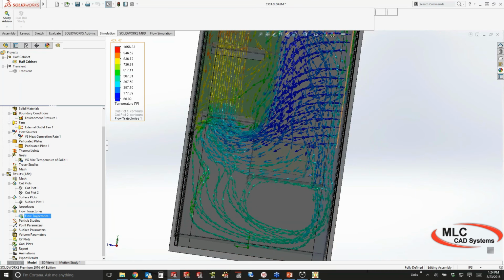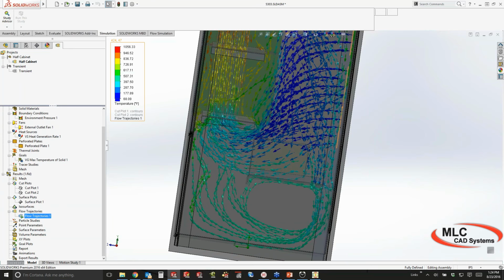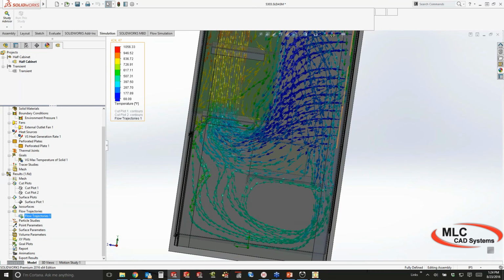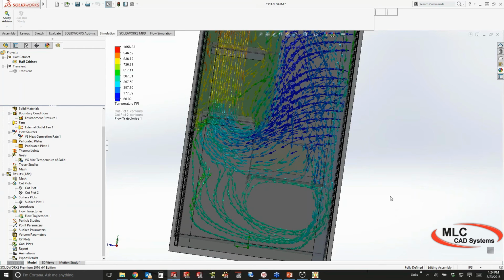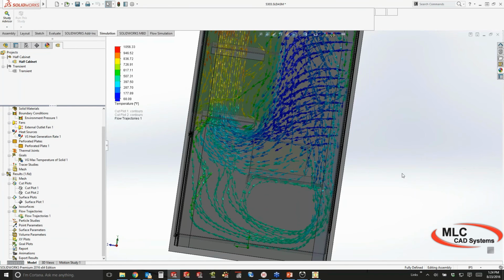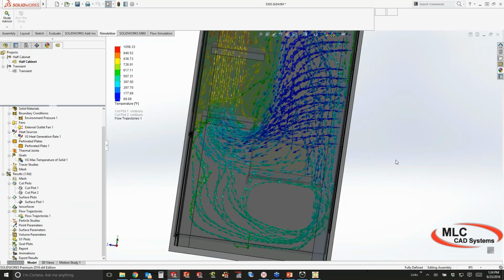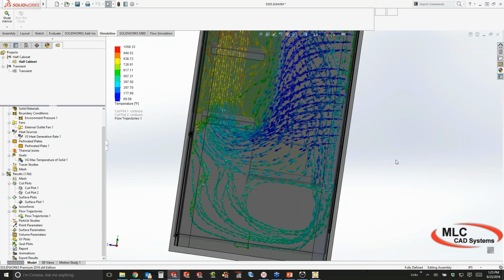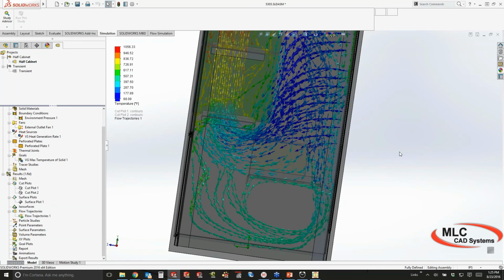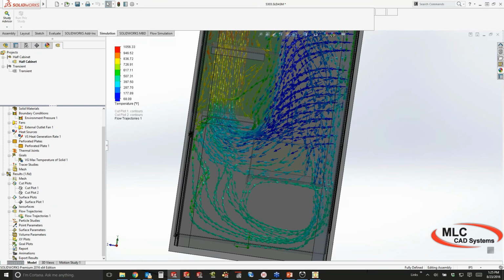That slow recirculation is not very efficiently removing that heat. And so anything that's down there that's generating a burst of heat, and there actually isn't anything hot down there, it just happens to be stagnant air, we're going to see some problems evacuating that. And by using this tool, we're able to make minor changes, things like baffles, things like redirecting that air, and making small design decisions that actually create a more efficient design.